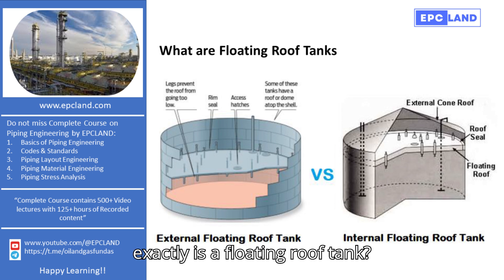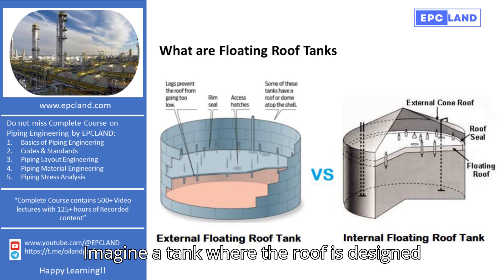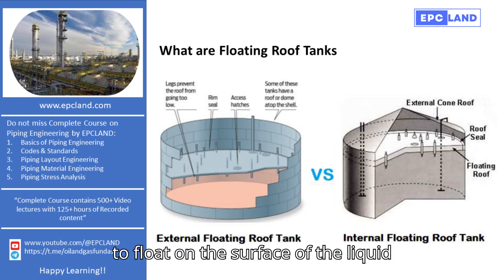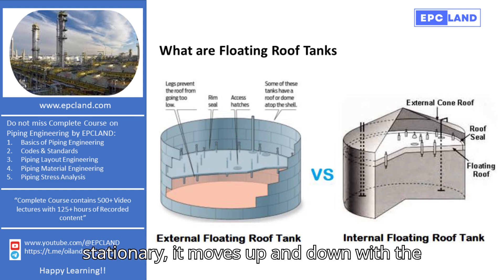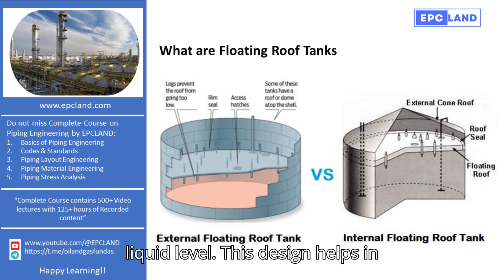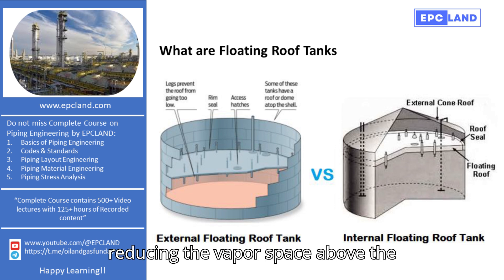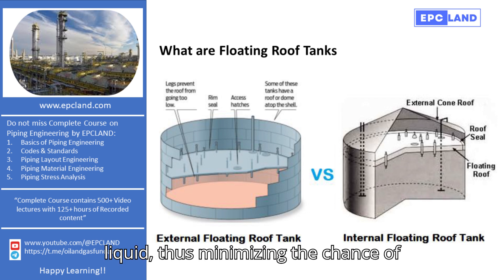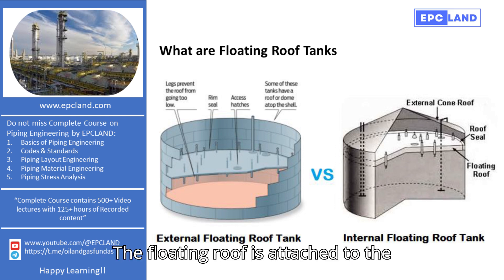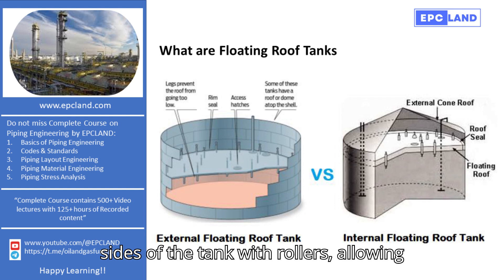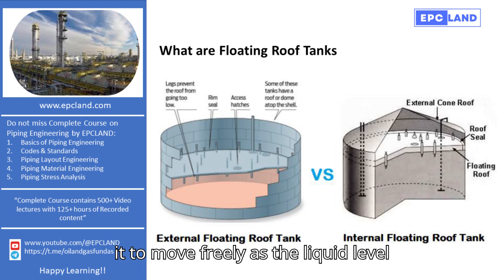What exactly is a floating roof tank? Imagine a tank where the roof is designed to float on the surface of the liquid inside. This roof is not stationary — it moves up and down with the liquid level. This design helps in reducing the vapor space above the liquid, thus minimizing the chance of vapor escaping into the atmosphere. The floating roof is attached to the sides of the tank with rollers, allowing it to move freely as the liquid level changes.